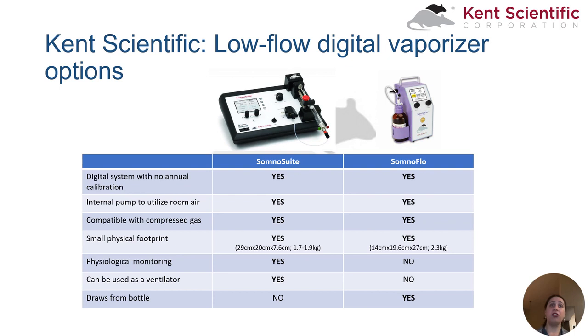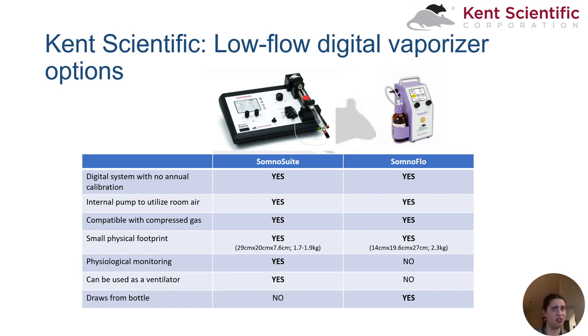We offer two systems: the SomnoSuite and the SomnoFlo. Both are digital systems with no calibration required, can utilize either room air or compressed gas, and have a small physical footprint. However, the SomnoSuite includes physiological monitoring and can also be used as a ventilator if needed, but requires a syringe mechanism to fill. The SomnoFlo can draw anesthetic straight from the bottle. So, it's your fancy Lamborghini versus your 2014 Toyota Corolla — both will get you where you want, but you might need the Lamborghini sometimes.